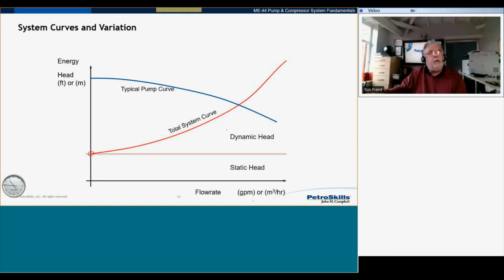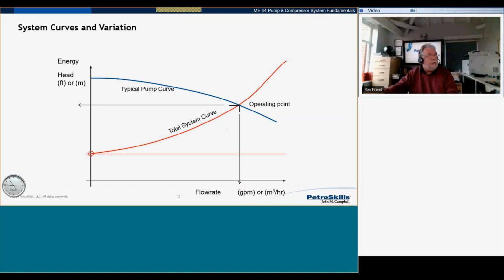I overlay now my pump curve onto that system curve. And the thing to remember is your pump will operate where the pump curve and the system curves cross. That's always true. So that's your operating point. Easy. So this is our design flow. This is now my design total dynamic head. And a lot of the time, that's all we do. So we go to the pump vendor who say, yeah, I'll have that pump, please, because that's what I want. That works.